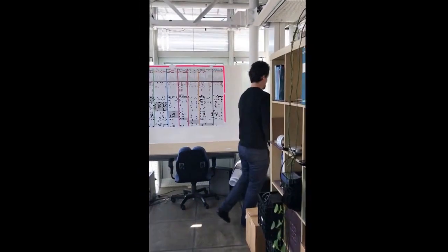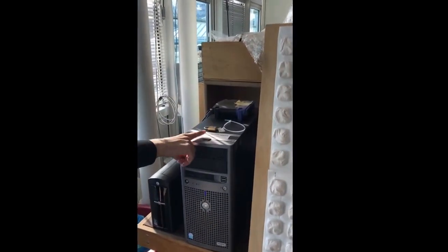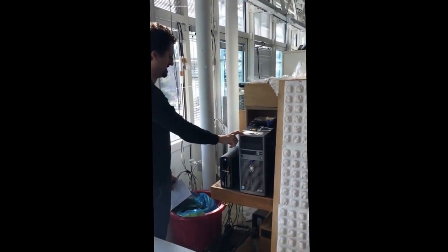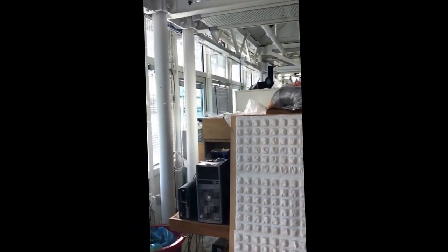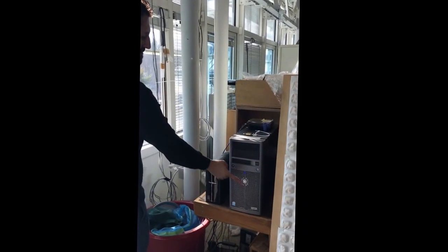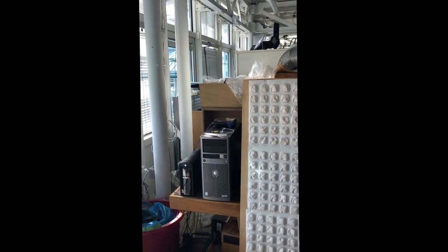Go to this location. Here it is, right at the corner, clearly labeled Automated Logic server. You see, it's the Automated Logic server. This is only for the SEMCO, right? And if the SEMCO server is down when you try to access the web server, most likely you just have to reboot this machine. Okay. Just let me know.